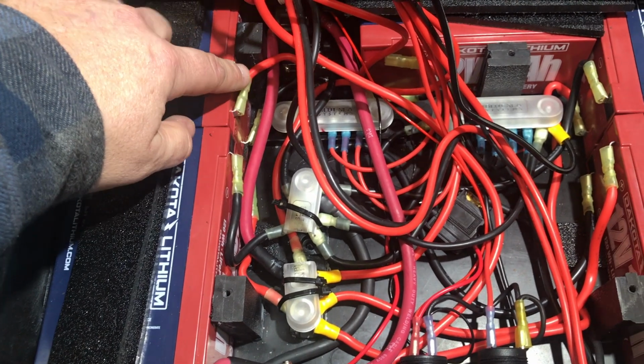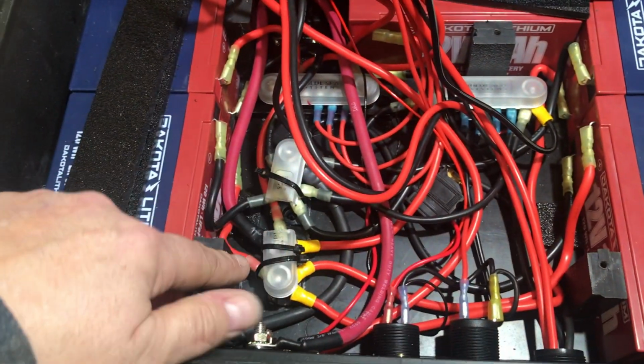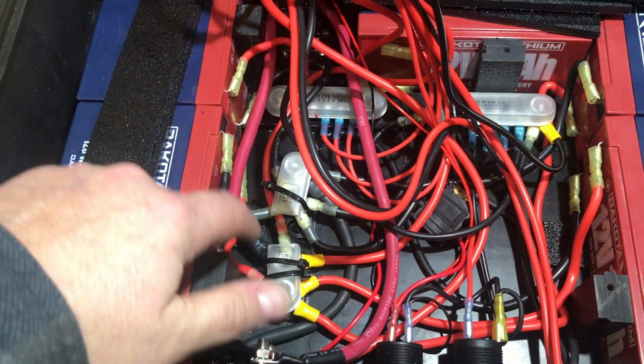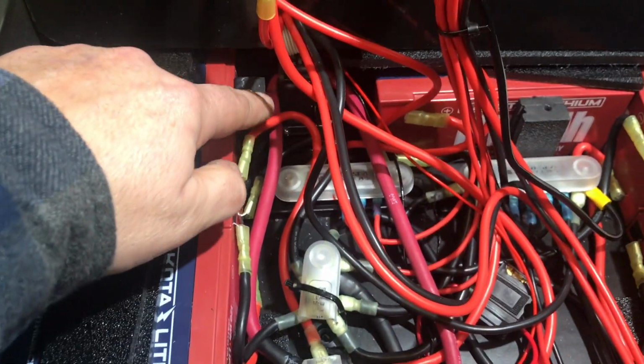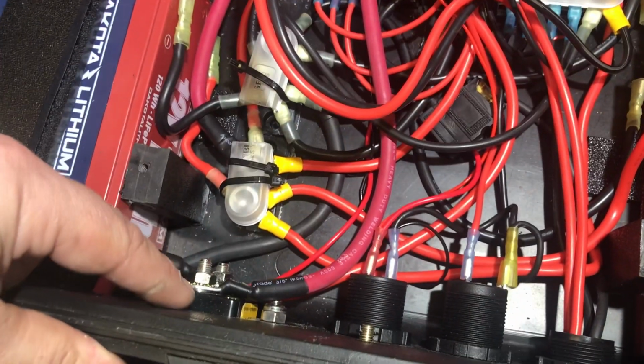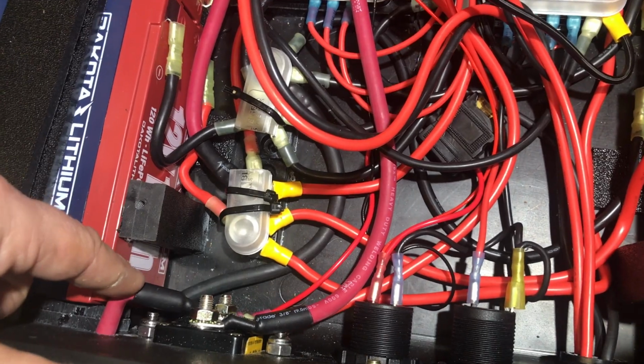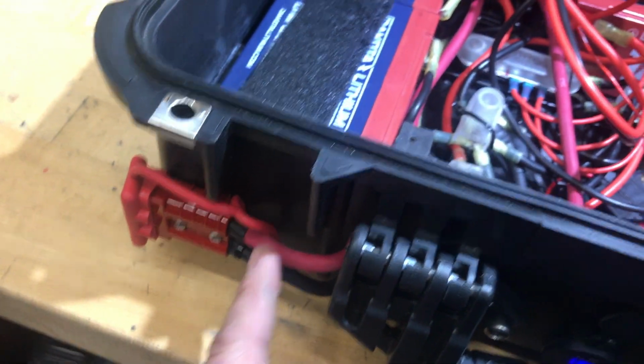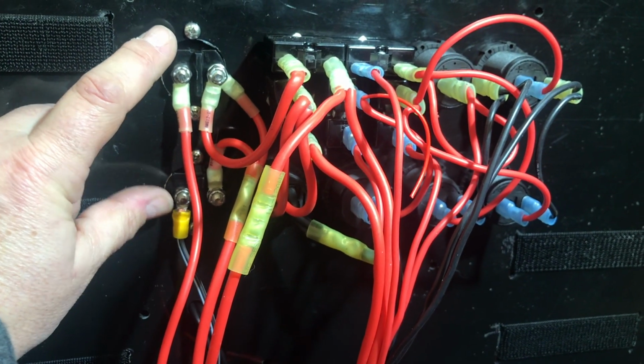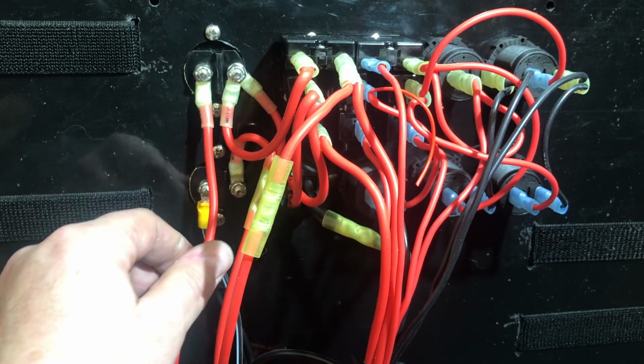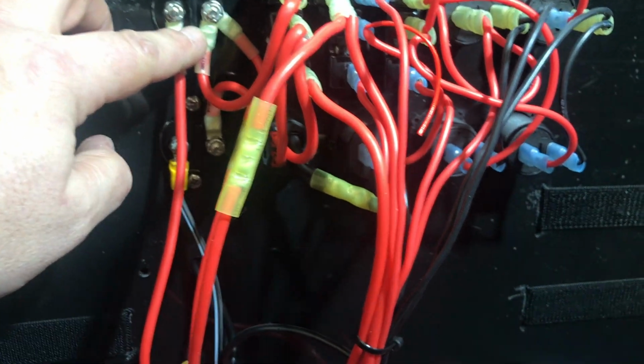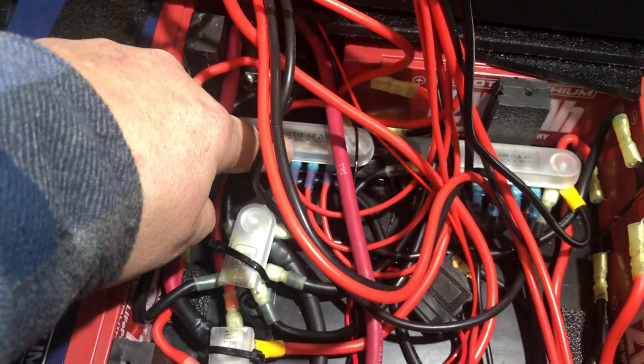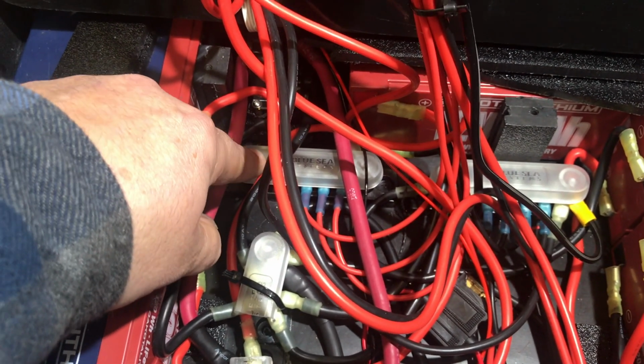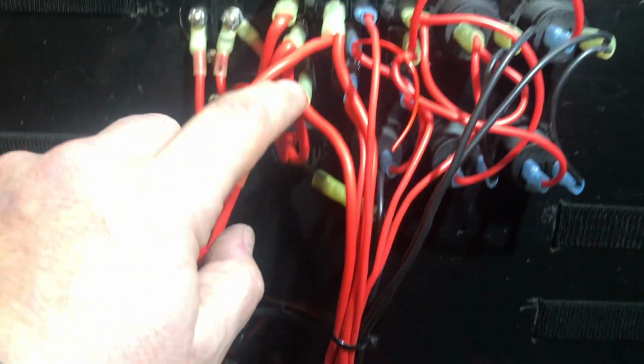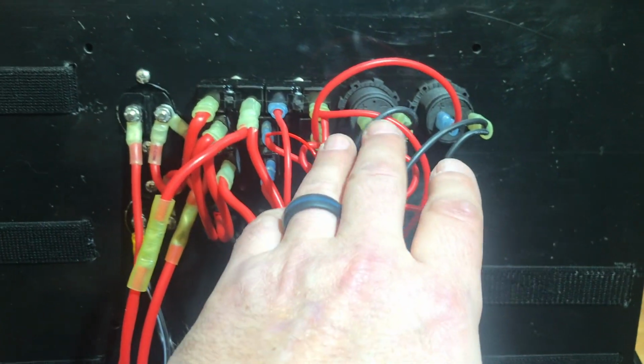Each positive on each battery runs back here all the way around, all 10 gauge wire connecting into this block, and then a large 6 gauge cable comes out of here, goes back through my hall sensor in the back to the front, and onto the input side of my main circuit breaker. It comes out of the circuit breaker into my high current outlet on the outside. Then there's a line going up that feeds two main circuit breakers, one for the inverter and one for everything else, using pretty heavy gauge cable, 12 gauge, here. Then it goes from this main circuit breaker back down into another smaller screw terminal positive distribution block, which feeds individual circuits that go up to their circuit breakers, then out of the breakers into each individual outlet.